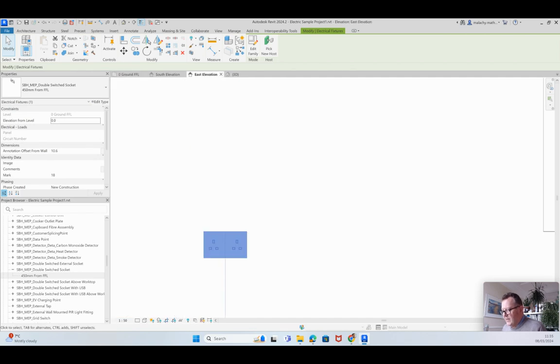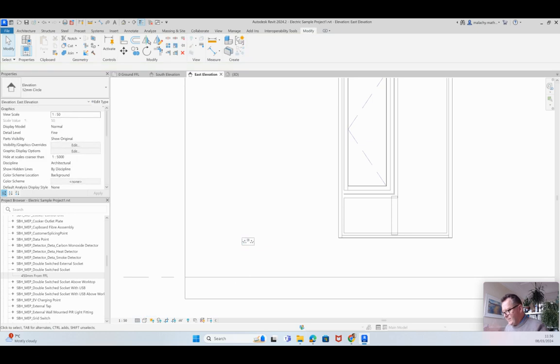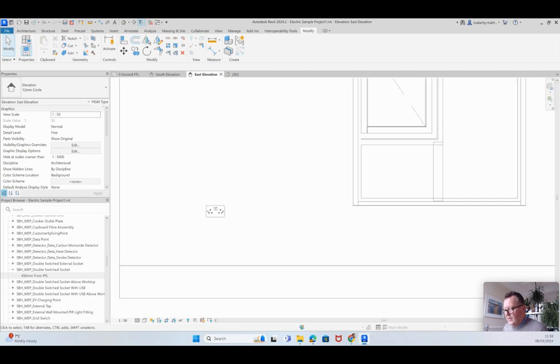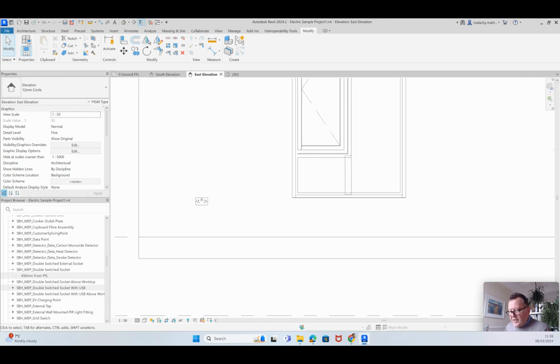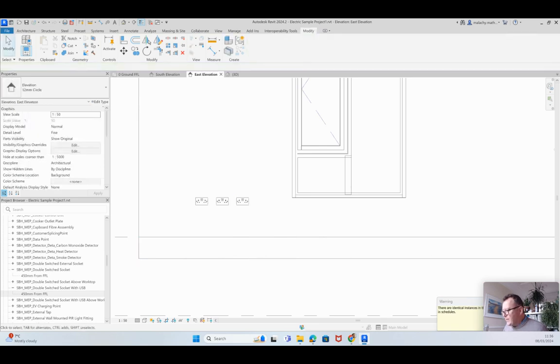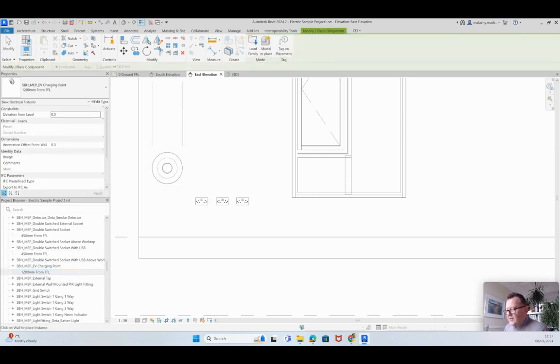Back in the east elevation — the reason you might not see the socket is the detail level. If you're in Coarse, you won't see it; switch to Fine and there it is. No need to move it off the wall — that was the socket. You've also got various socket types including one with a USB port. The standard height above ground floor level is 450mm, and that reference line is what positions them at the correct level automatically.